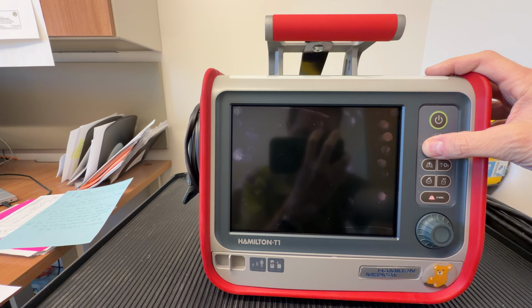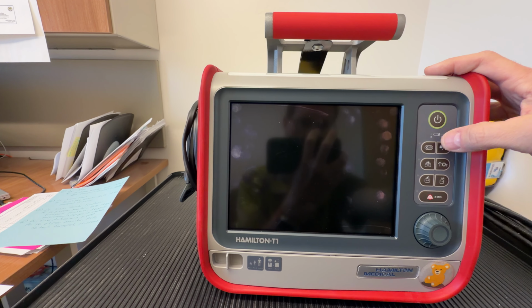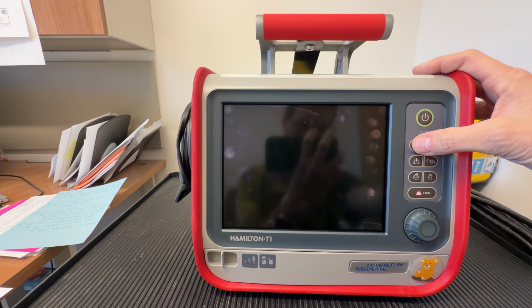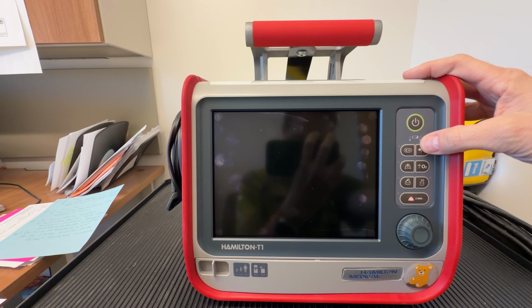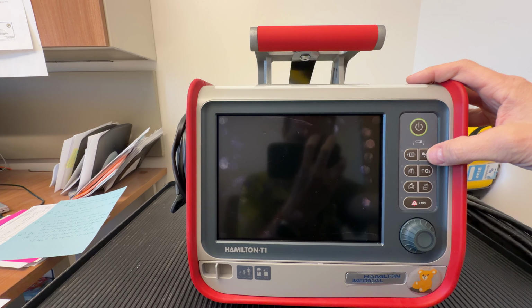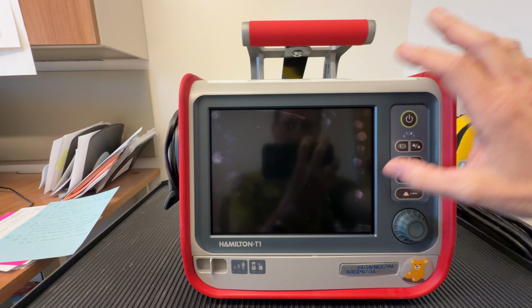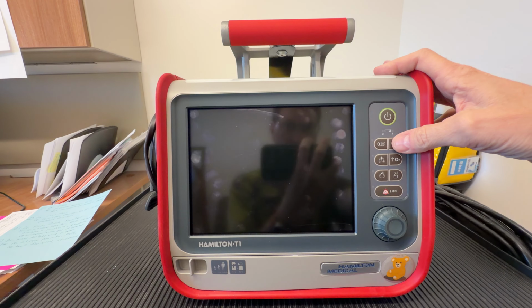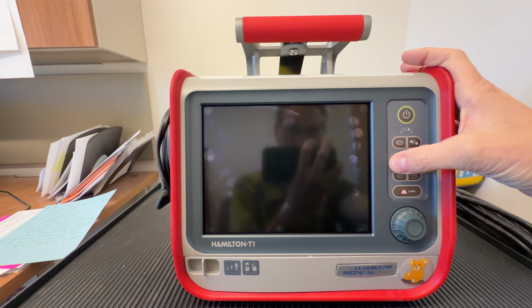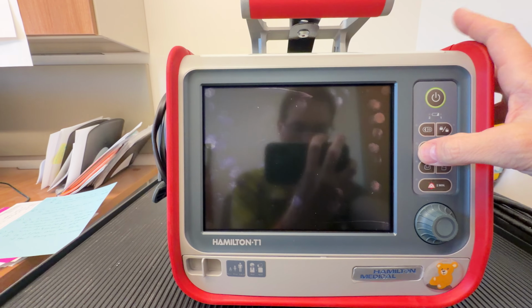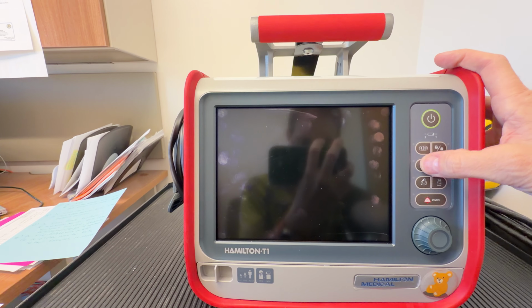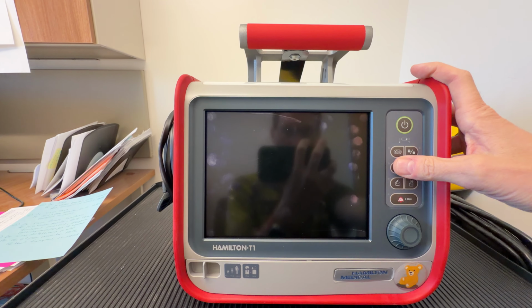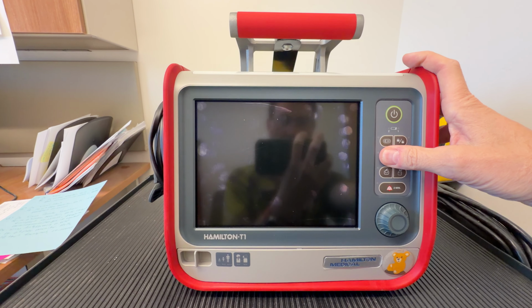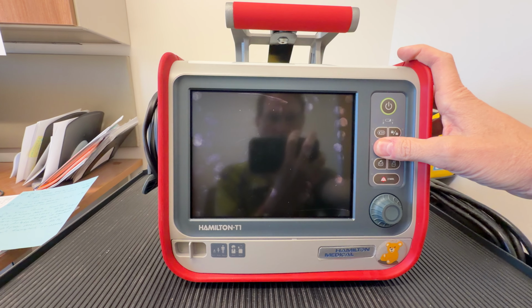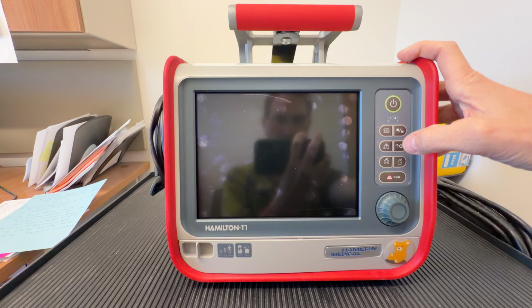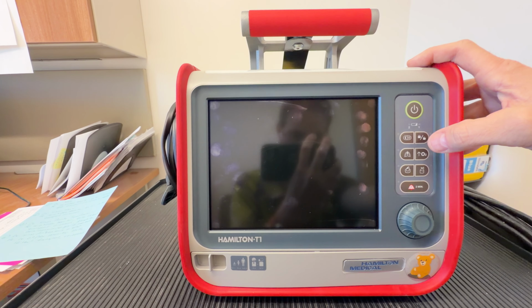Moving on, this is the day-night key. This switches between day and night brightness modes or settings. This button right here is the screen lock/unlock. So you hit that to prevent any inadvertent changes of settings from occurring. All right, this little lung icon here is a manual hold. This is an inspiratory hold. Take a breath and hold it at the end of the inspiration. And of course, you can use that to get a plateau pressure as well.